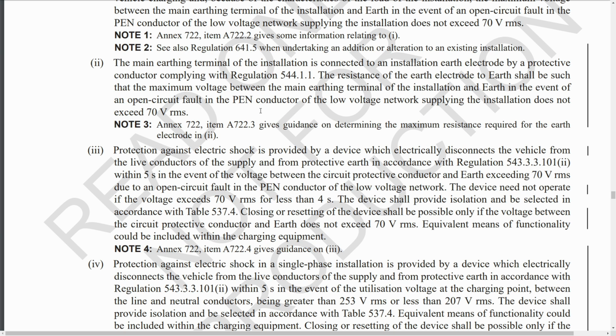And the idea of this is that if the PEN conductor goes open circuit and the voltage on it rises, because you've got this substantial earth mat connected to it, that will keep the voltage down as low as possible, and it won't exceed the 70 volts.